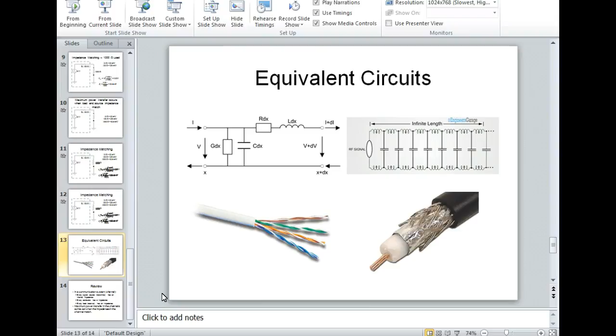So this is how much we... by the way, if a signal conductor cable ever crosses a power cable, you're supposed to cross it at 90 degrees. You're never, ever supposed to parallel a signal conductor with a power conductor. You're never, ever supposed to run a signal conductor in the same conduit as a power conductor, because now you're going to radiate the whole length of the cable. If you run it at 90 degrees, the only problem you're going to have is right there where those things cross at 90 degrees, right?